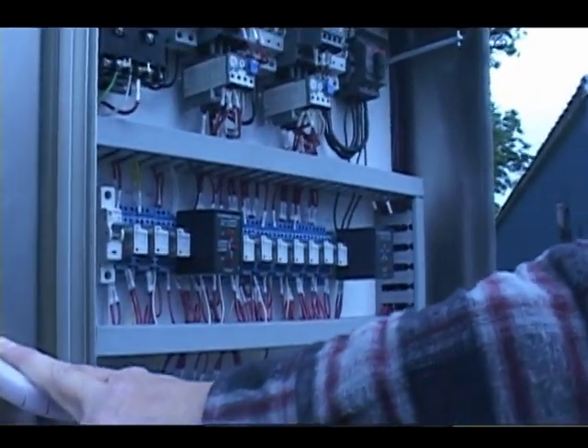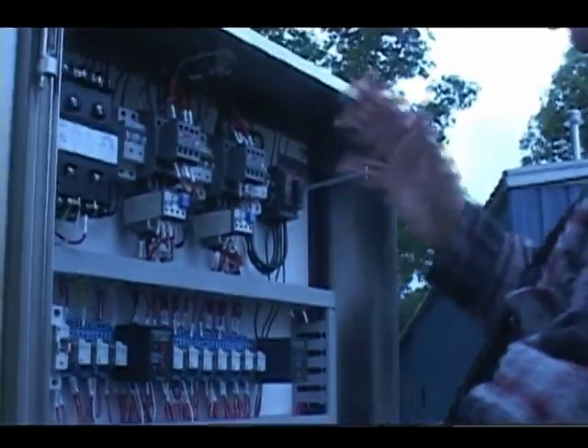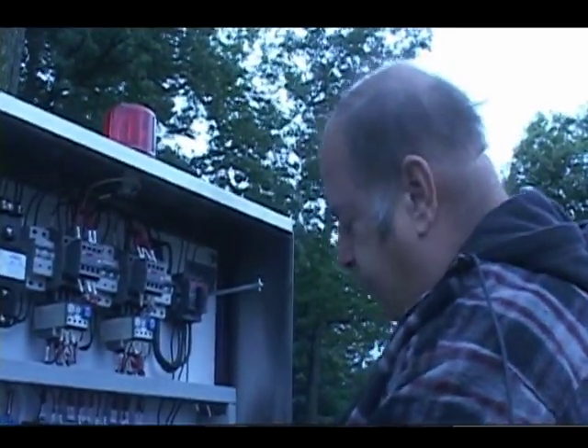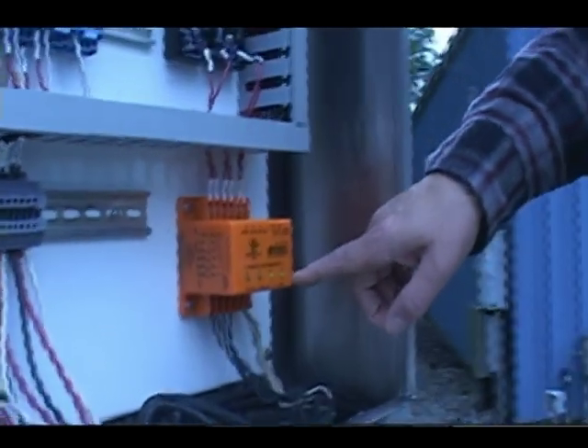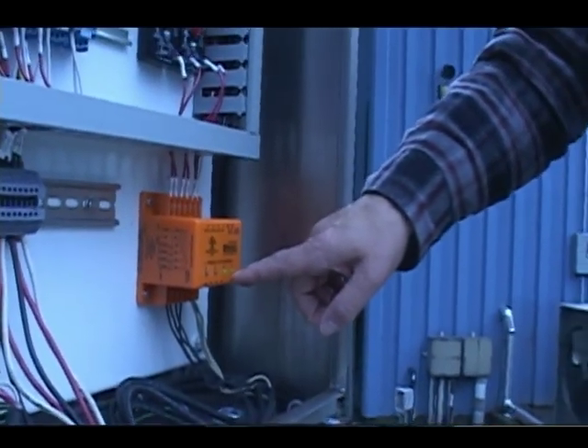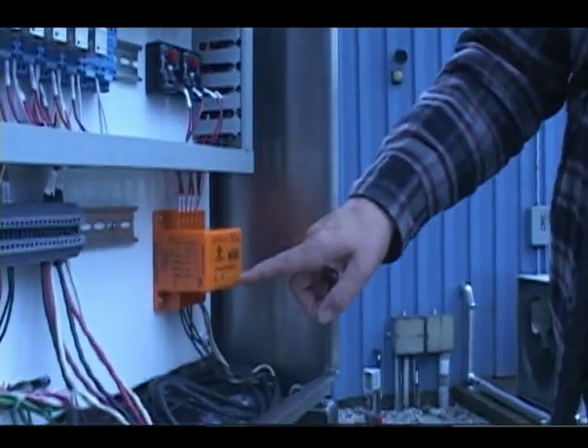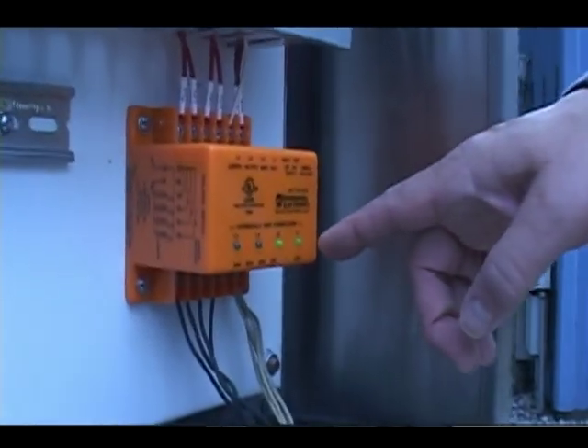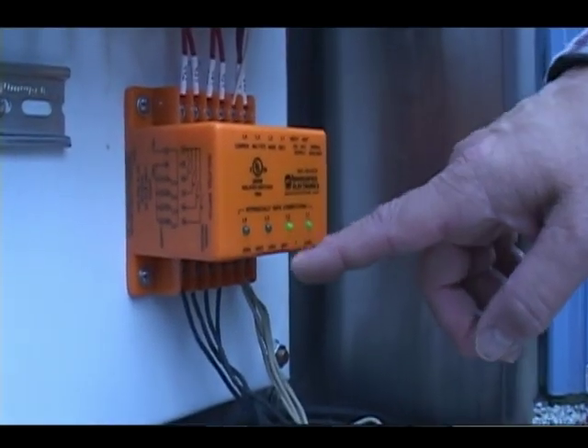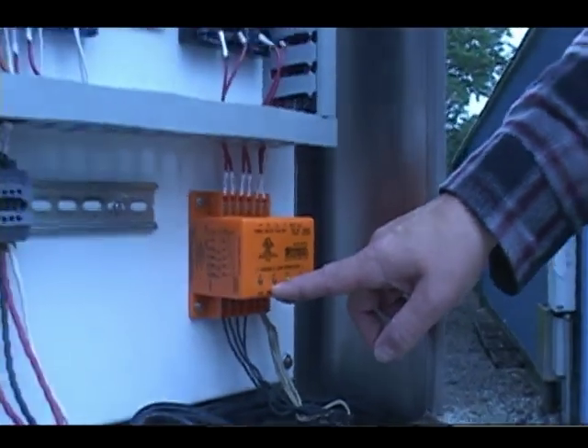Right? Now, as the level in the wet well fills, more and more of these lights on the intrinsically safe barrier are going to come on. Right now we have 2 of them. Right? Which means that the low is made and the low. When this light comes on, that is the lead pump call. This is the lag pump call.